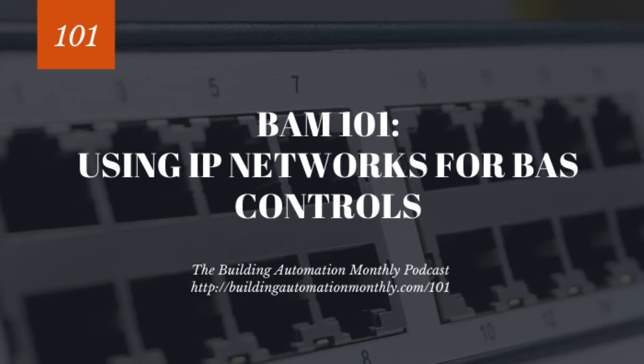No, it makes perfect sense. When you build these controllers, you typically order parts from your standard electronics wholesaler and put them in your controller. You're right, when it doesn't have power, it doesn't pass communication on. But controller manufacturers are getting smart, and now they'll put a relay in, so when it detects no power, it just connects all the wires together.